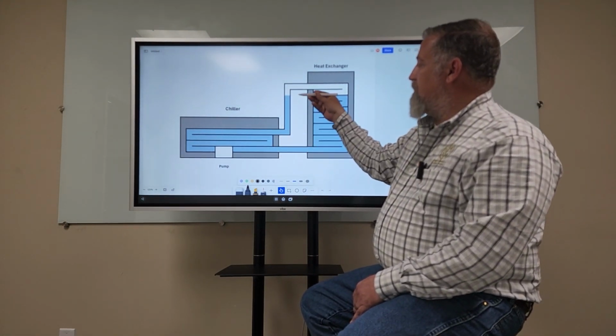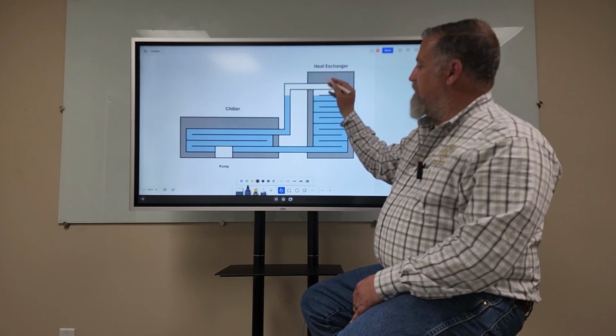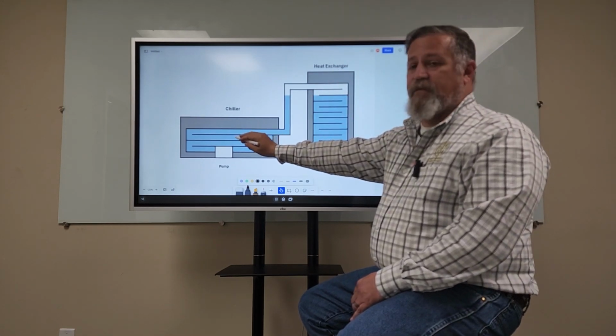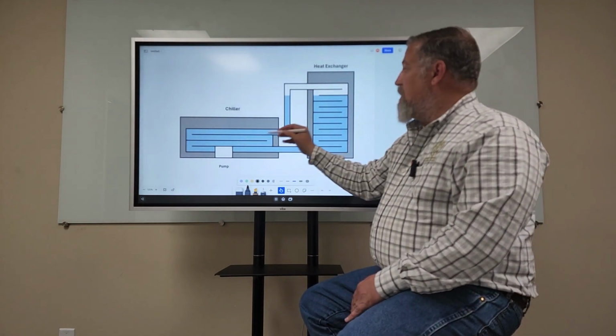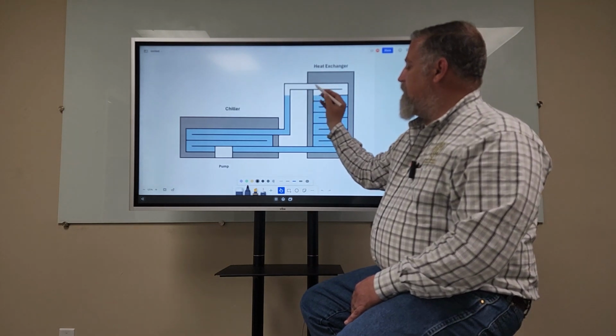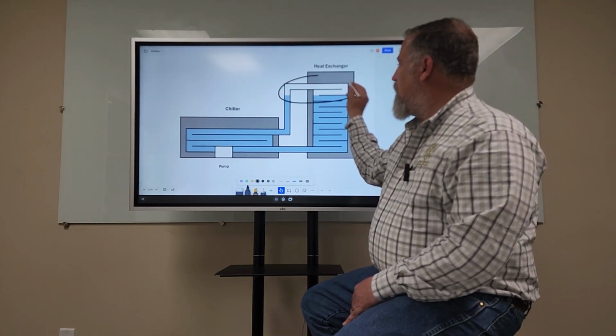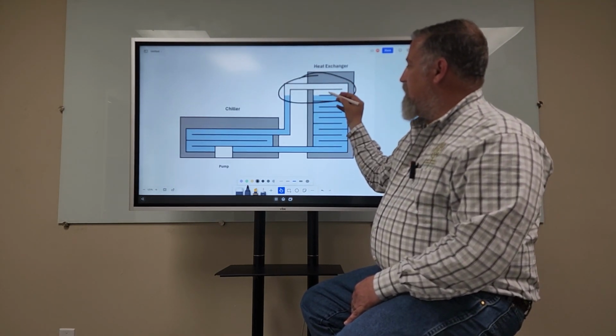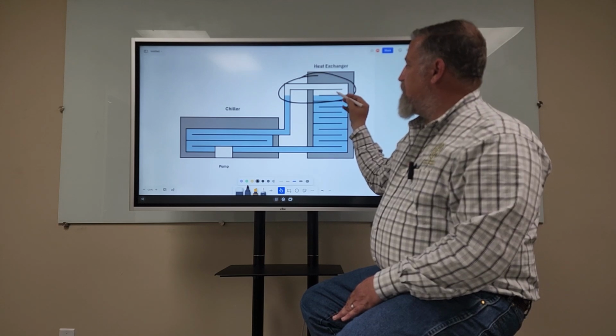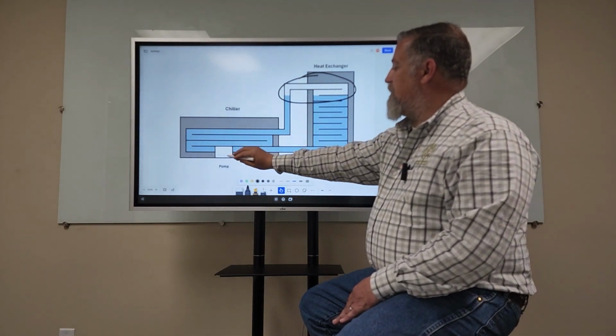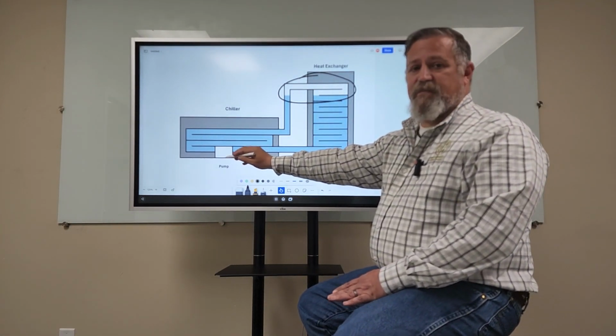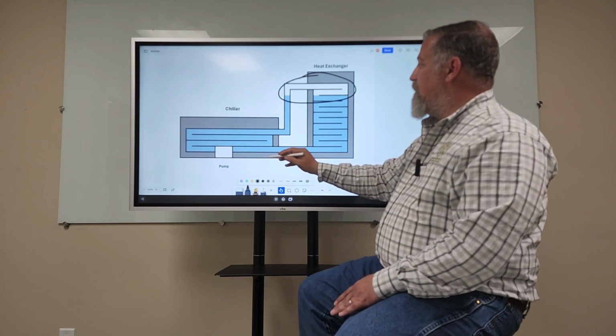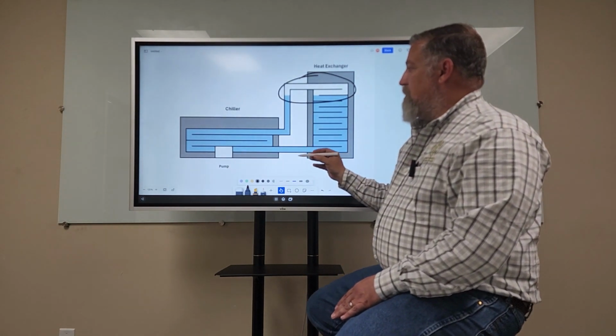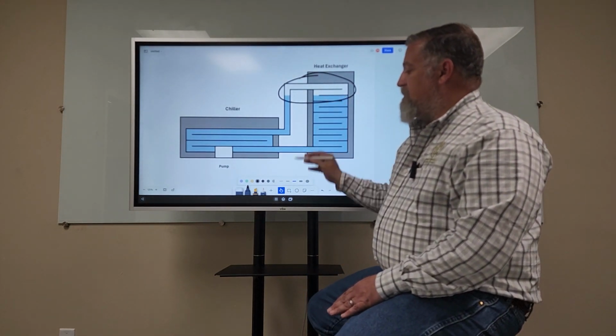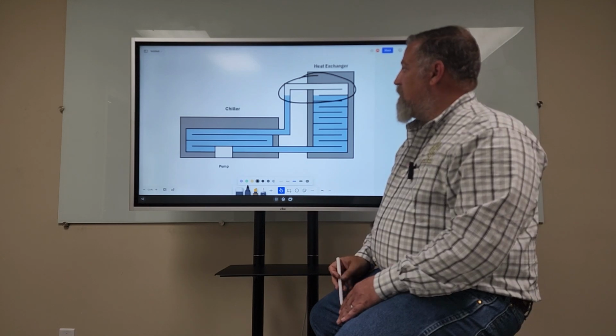Okay, so we have a pretty large air pocket still at the top of the heat exchanger. You can see that our chiller is full, but we're not done. We've got to get this air here out of the heat exchanger. If we try to run this unit at this point, this air pocket's going to move back around and it's going to get to your pump. And it's going to cause your pump to cavitate and you're not going to have any flow. So again, we're not done yet. We've got to get to the final part.